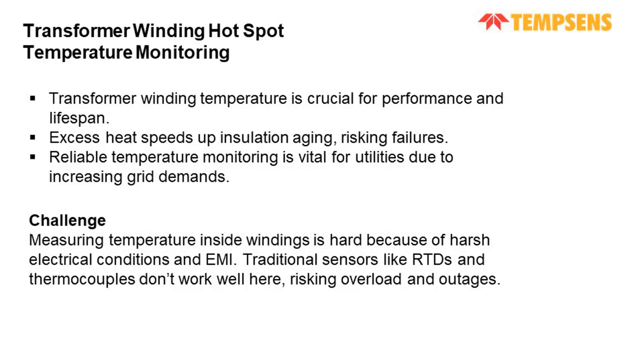When the transformer gets too hot, its insulation ages faster, which can lead to early failures. And with the grid becoming more stressed due to higher demand and more assets being pushed to their limits, keeping a close eye on temperature is more important than ever for utilities and transmission and distribution companies. But there is a challenge in this. Measuring the temperature inside the transformer winding isn't straightforward. These zones are electrically harsh environments with very high voltages and strong electromagnetic interference, or EMI.